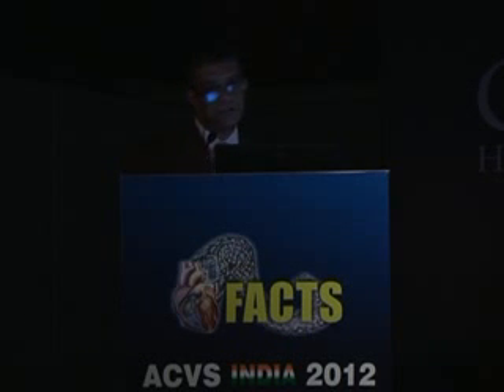The oximetry machine is a very important part of our cath lab. Every pediatric cath lab should have this machine. Unfortunately, surprisingly, it has become so difficult to procure. Remember that it is not the same as the blood gas machine, because the oxygen saturation that we get from the blood gas machine, which is available in most hospitals, is a derived parameter, whereas oximetry machines actually measure saturations directly.